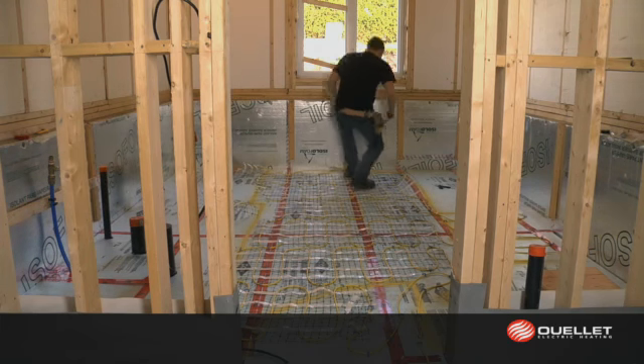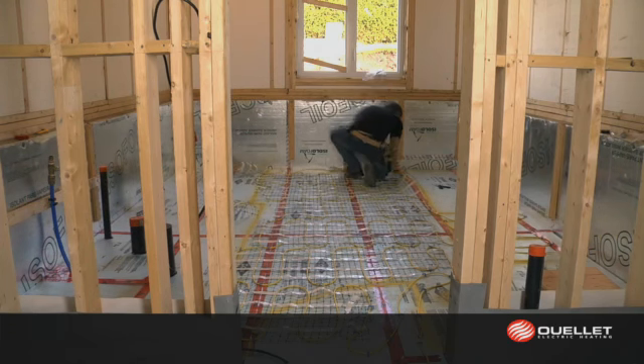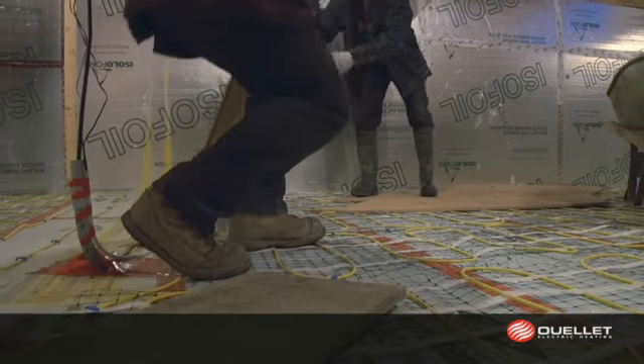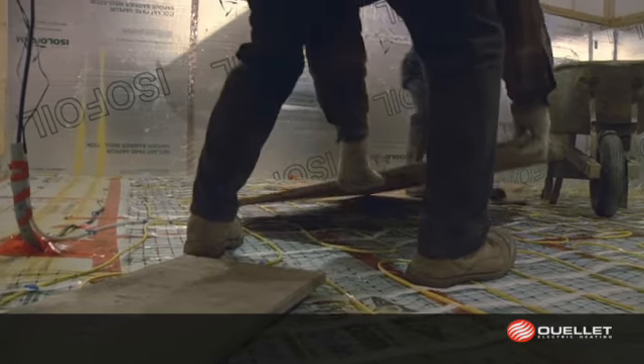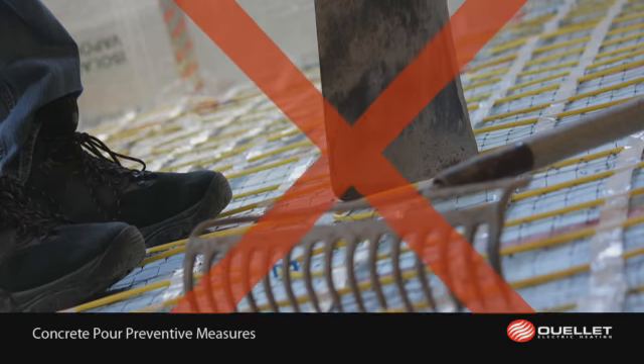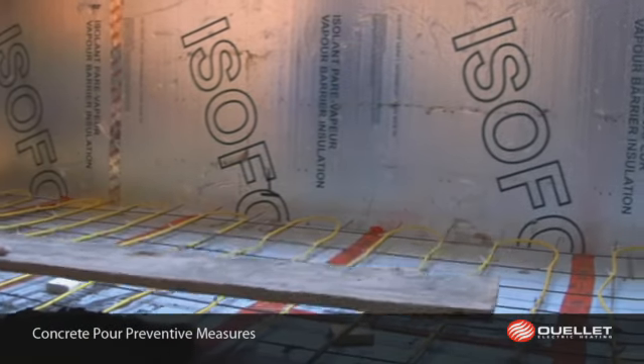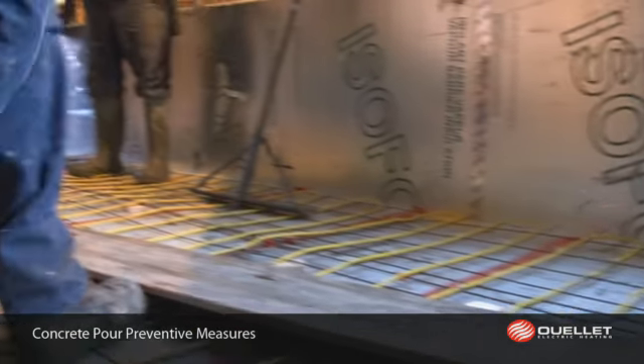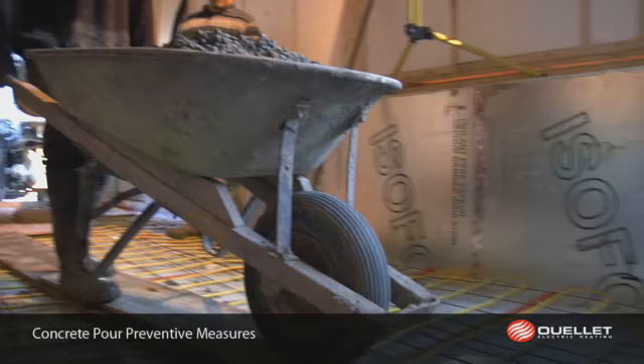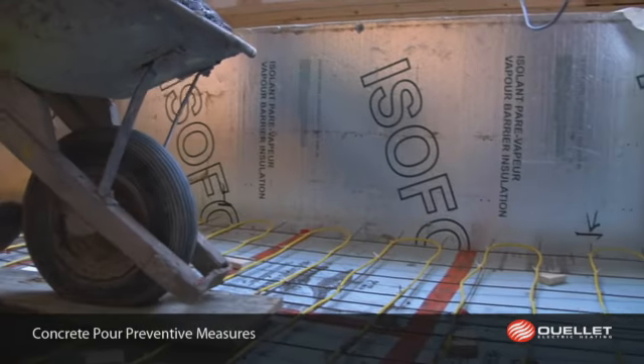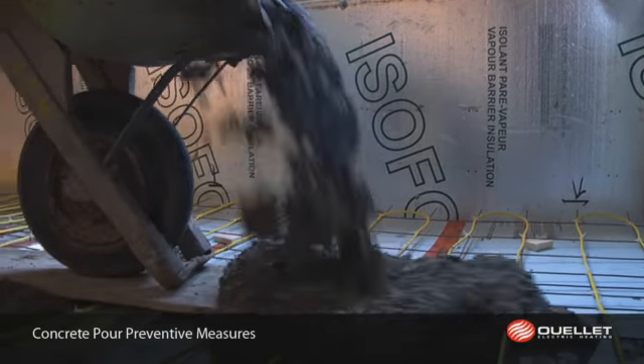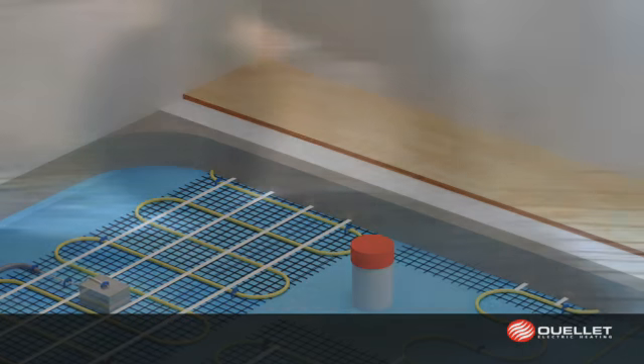The robust construction of the cable allows walking freely on it. However, a few preventative measures should be taken to make sure it will not get damaged by tools found on the building site. When using a wheelbarrow to transport the concrete, always place a plywood sheet on top of the installation on which you will be able to circulate while protecting the cable.